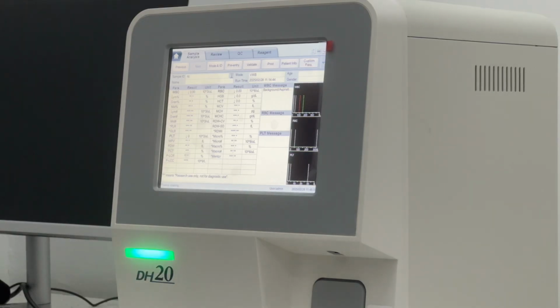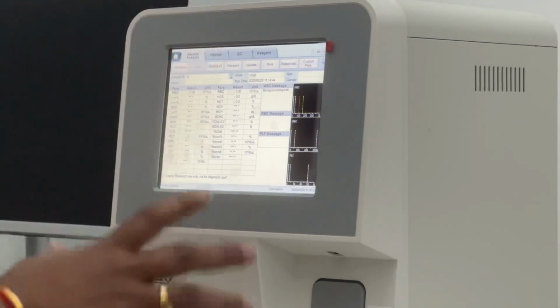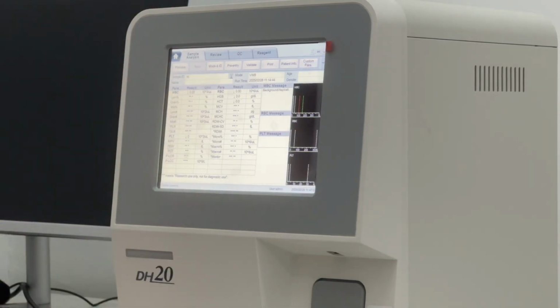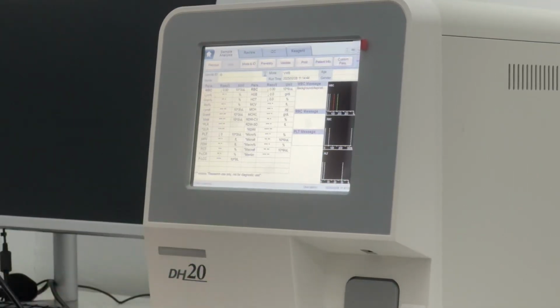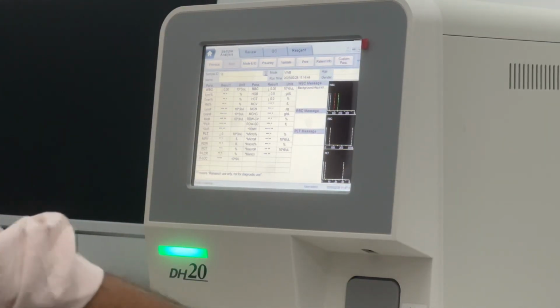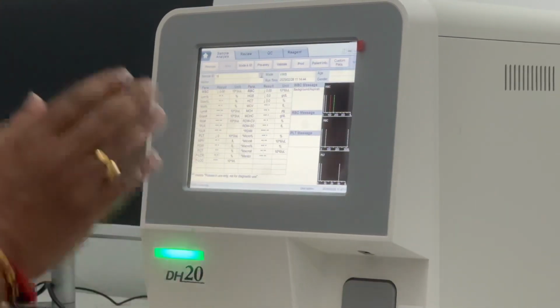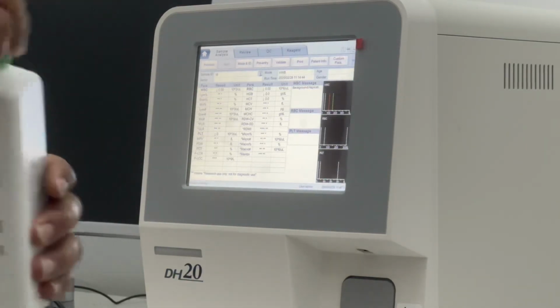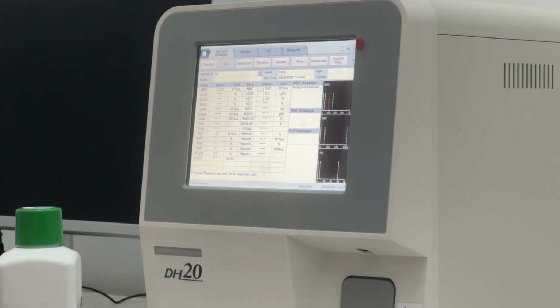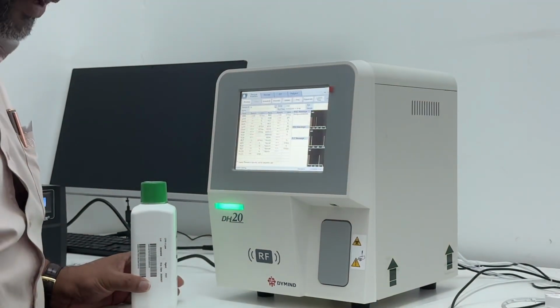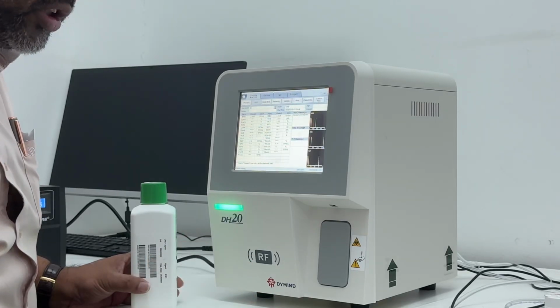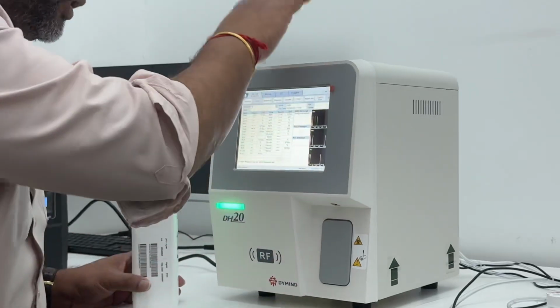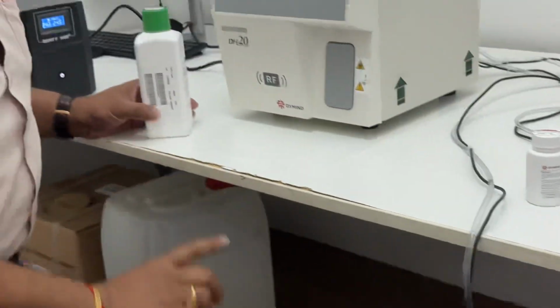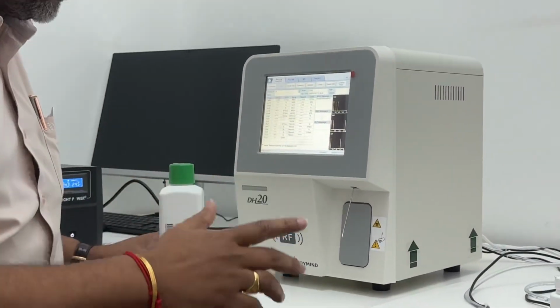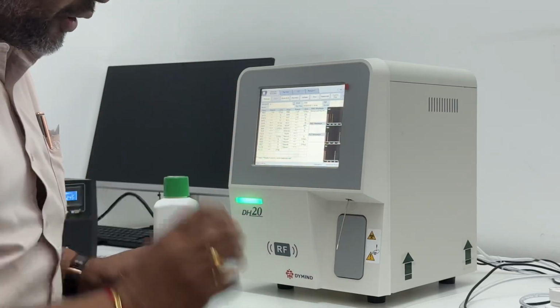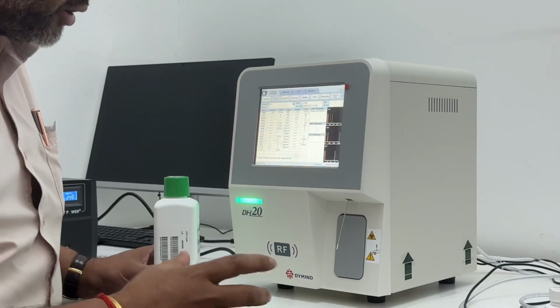Okay, while waiting, I can explain to you all. This machine is actually a very smart machine, something like our telephone. The diluent or the lyse, not the probe pencil, not this one. These two reagents, diluent and the lyse bottle, which is this, these two will work. The manufacturer designed it such a way that we need to use the original diluent from the brand called DYMIND for this particular model. Why? Number one, because anything regarding the reagent, the stability is very important. So for that reason, we need to use the correct reagent and the correct models for the reagent.